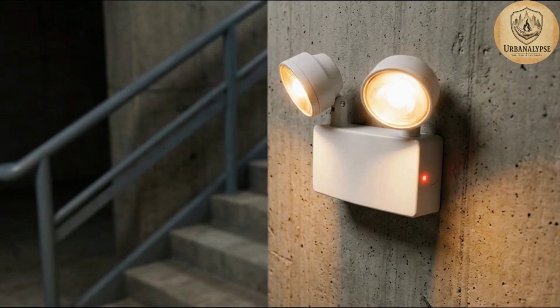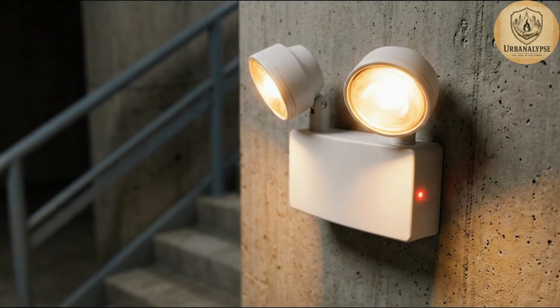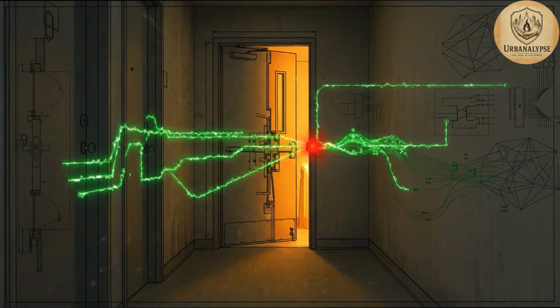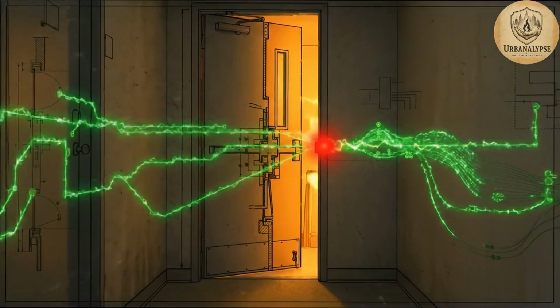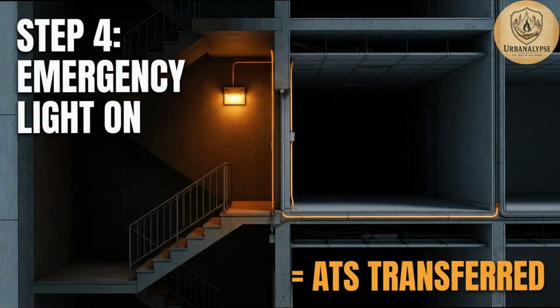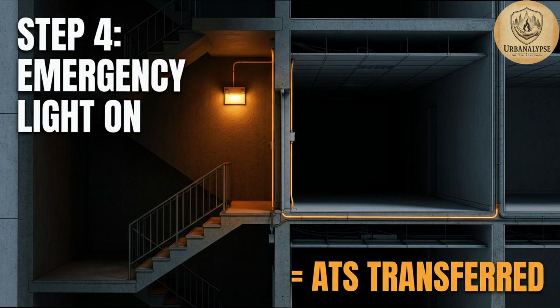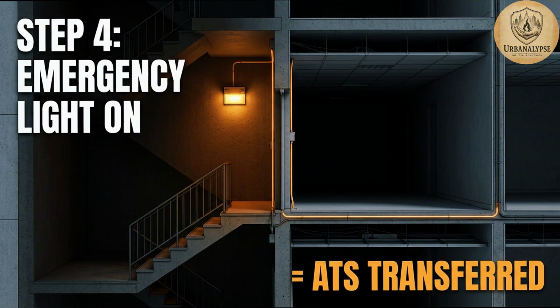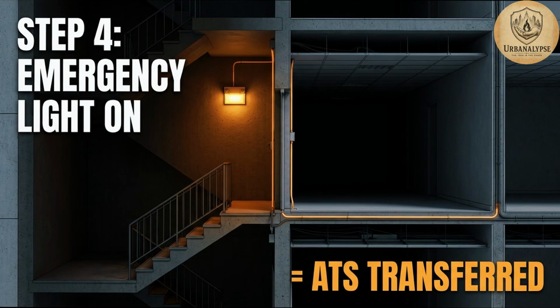By minute 15, check the nearest emergency lighting fixture in your hallway or stairwell. If stairwell lights are illuminated, but your unit hallway stays dark, the ATS transferred successfully and the failure is isolated to non-emergency branches only, not the whole system.